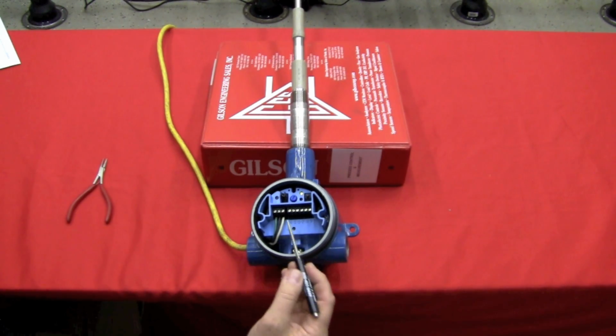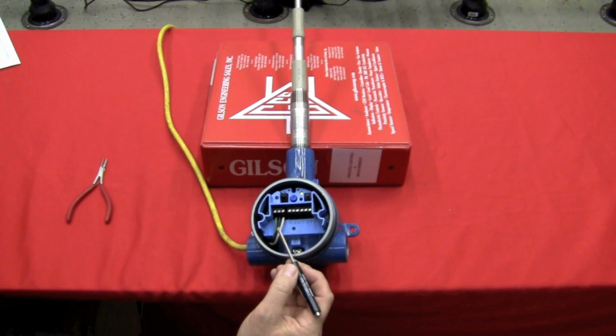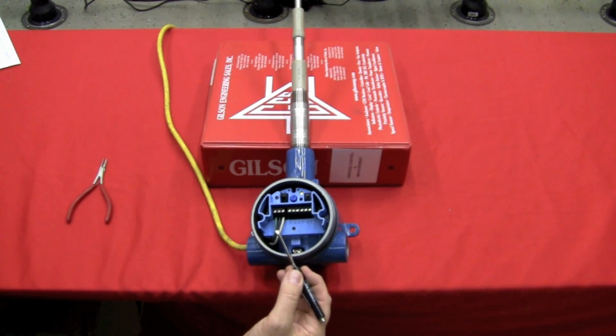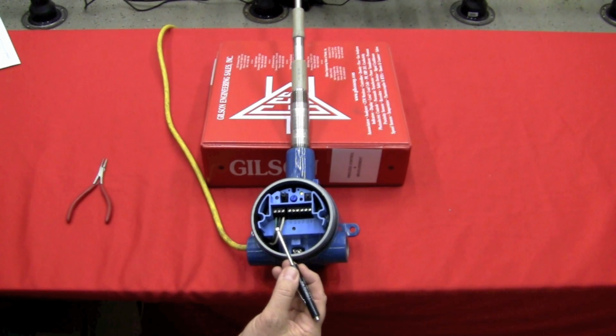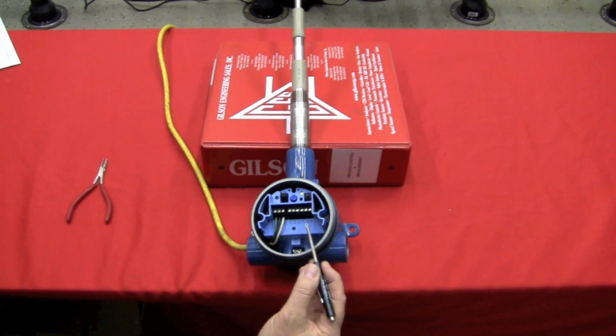First off, we have two terminal blocks on the bottom here. The terminal block on the left here is your universal power supply. We can take both AC voltage and DC voltage. You basically wire what you have and it'll sense it for you and you're good to go. Makes it very, very flexible for field installations where you might have 24 volts in an area and in another area you might have 110.